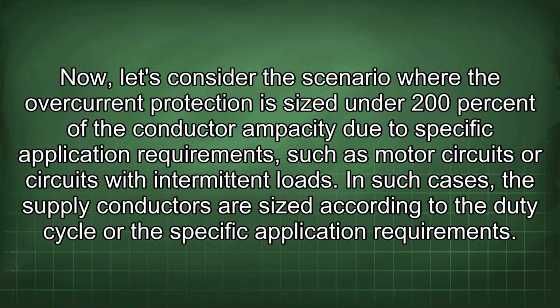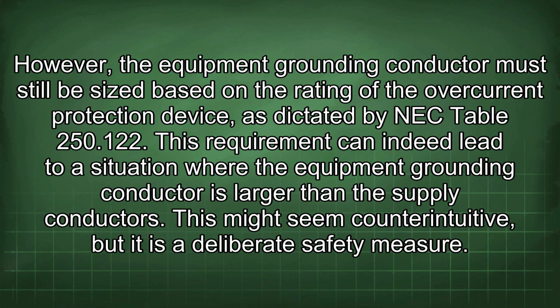Now let's consider the scenario where the overcurrent protection is sized under 200% of the conductor ampacity due to specific application requirements such as motor circuits or circuits with intermittent loads. In such cases, the supply conductors are sized according to the duty cycle or the specific application requirements. However, the equipment grounding conductor must still be sized based on the rating of the overcurrent protection device, as dictated by NEC Table 250.122. This requirement can indeed lead to a situation where the equipment grounding conductor is larger than the supply conductors.